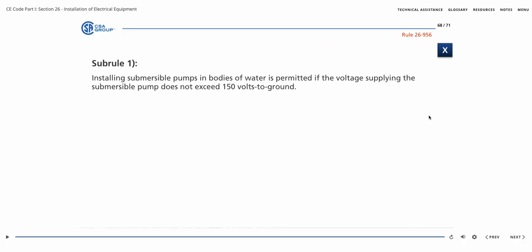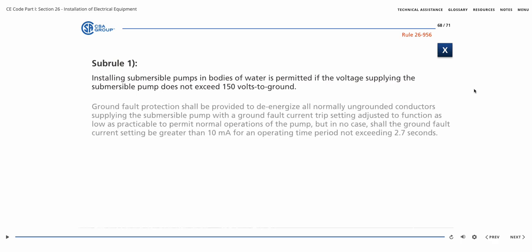Installing submersible pumps in bodies of water is permitted if the voltage supplying the submersible pump does not exceed 150 volts to ground. In addition, ground fault protection shall be provided to de-energize all normally ungrounded conductors supplying the submersible pump, with a ground fault current trip setting adjusted to function as low as practicable to permit normal operations of the pump. But in no case shall the ground fault current setting be greater than 10 milliamps for an operating time period not exceeding 2.7 seconds.